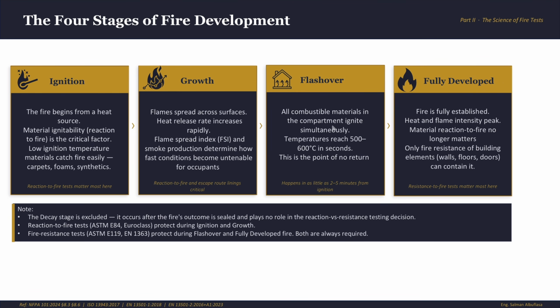Pre-flashover, you can survive. Post-flashover, it's a different story. Anyways, in the fully developed phase, fire is fully established. Heat and flame intensity peak. Material reaction to fire no longer matters, only the fire resistance of the building. Remember the medieval castle example? That's it: walls, floors, doors. How much can they contain the fire in one compartment? How long can they maintain their integrity? This is the domain of fire resistance testing.